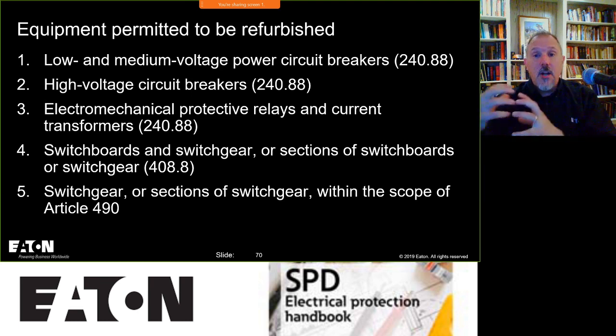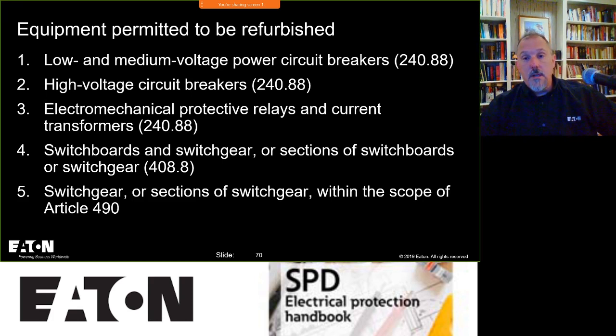And then what might hurt you is that if the code says the product shall be listed, and you remove the listing mark because you reconditioned it, that may prevent you from installing it per the National Electrical Code, because an electrical inspector is going to go, that's not a listed product, but it says it needs to be listed in this book. Now, having said that, not all products have to be listed. There's some misconceptions about that as well.